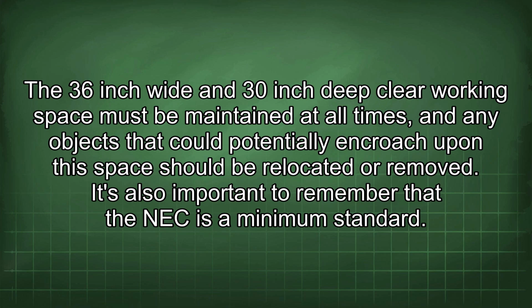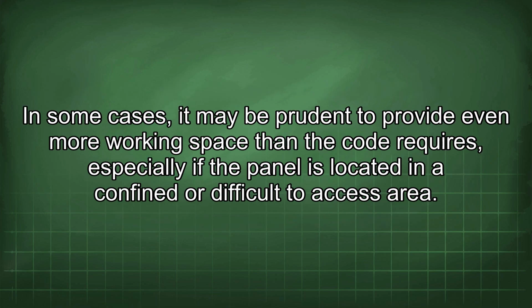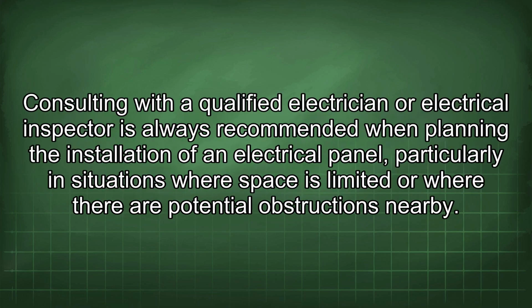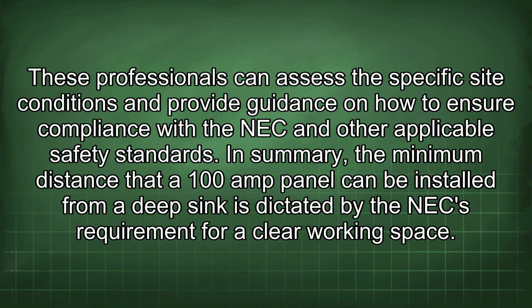It's also important to remember that the NEC is a minimum standard. In some cases, it may be prudent to provide even more working space than the code requires, especially if the panel is located in a confined or difficult access area. Consulting with a qualified electrician or electrical inspector is always recommended when planning the installation of an electrical panel, particularly in situations where space is limited or where there are potential obstructions nearby.